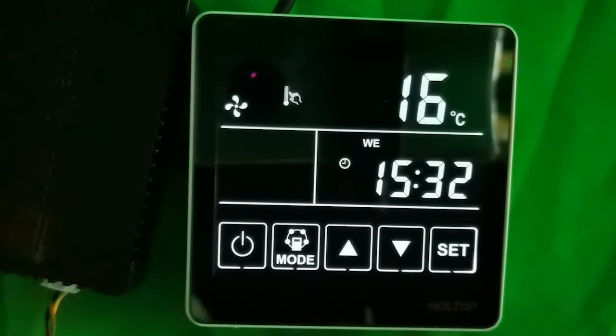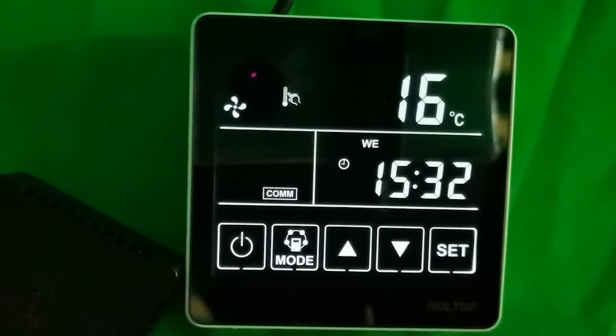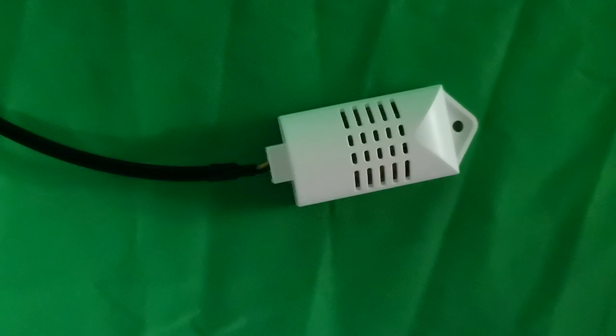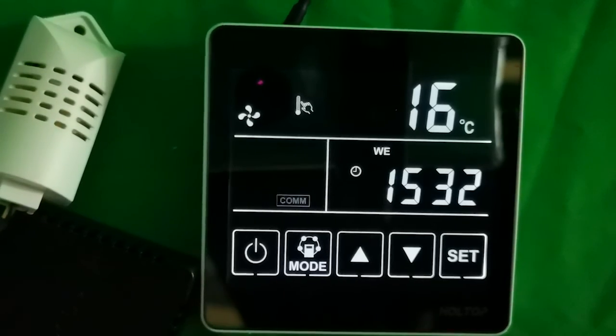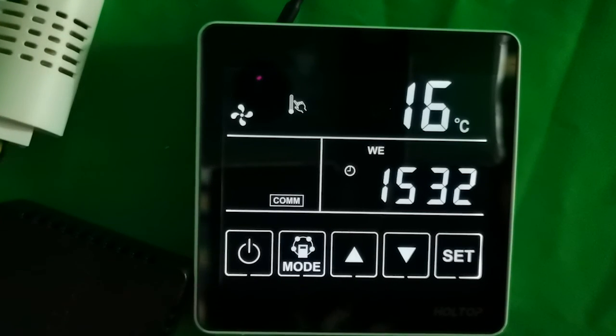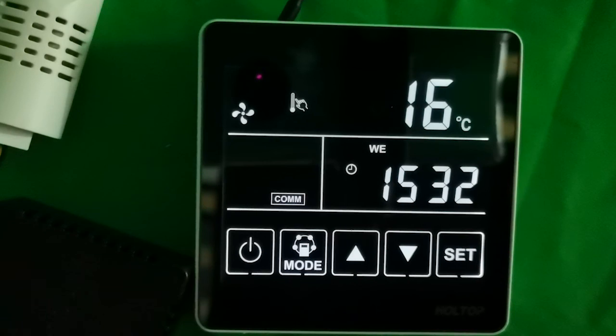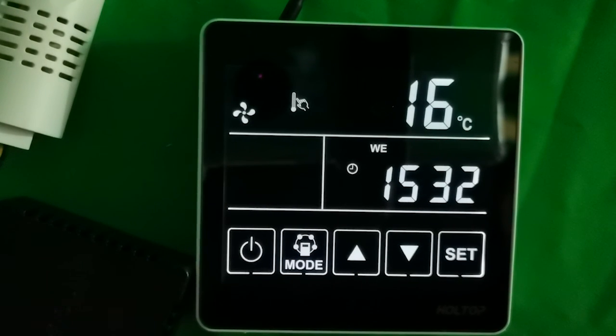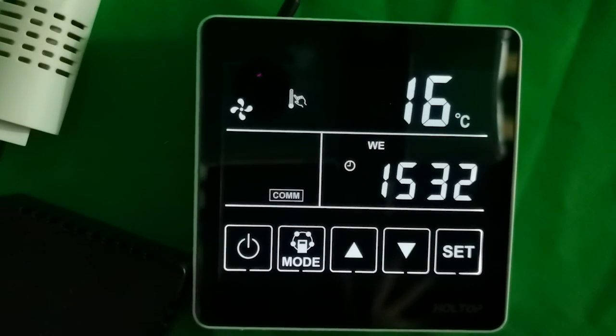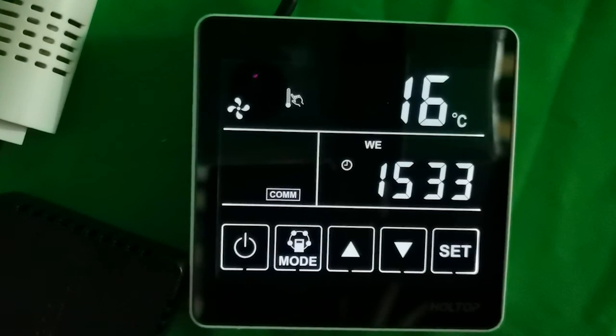Let's introduce the humidity control function — it's the same logic as CO2 control. Here's our humidity sensor, which is the same for both the advanced intelligent controller and this black cool controller. The humidity symbol will appear on the panel when the sensor is connected. The ERV units will run at highest speed when the humidity concentration is higher than the setting value. Under humidity control mode, end users can set the humidity concentration by pressing the up and down buttons, and the setting ranges from 50% to 100%.